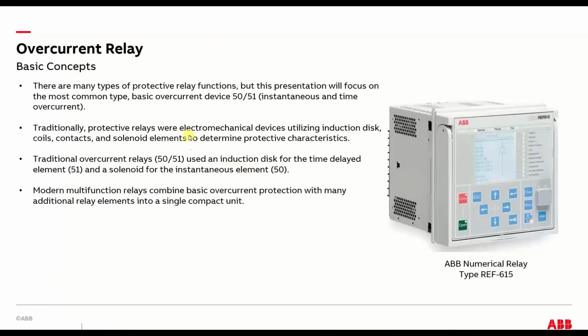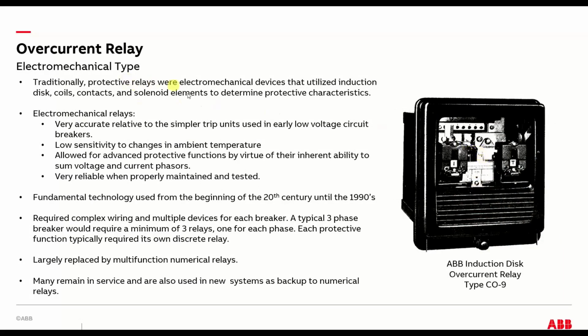Now we're finally getting to the overcurrent relays. Basically, I'm just going to go through this. There are many types of relays that do all kinds of different protection functions, but I'm keeping it really simple. It's just an overcurrent device. So this would be your 50, 51, 50 being instantaneous and 51 being your time overcurrent. Here's an example of the same multifunction relay, but in the next couple of slides, I'm going to start out with the electromechanical and then move my way up into numerical, multifunction.